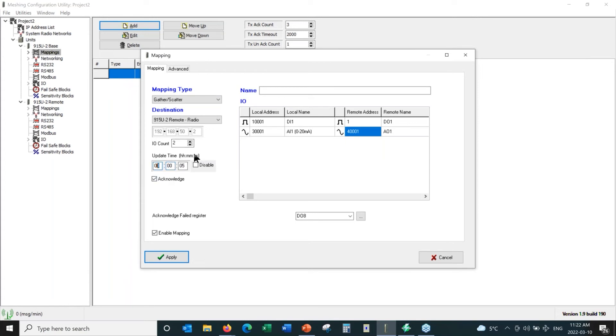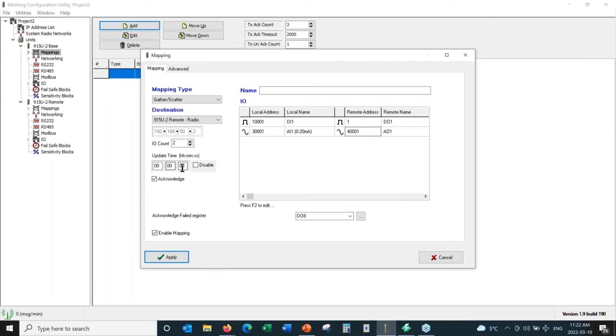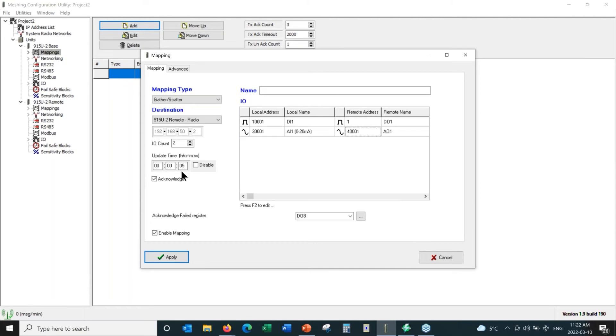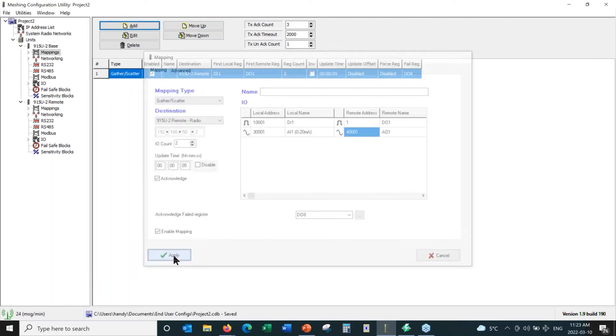With the update time set to five seconds, this radio will transmit every five seconds even if values don't change. For customer installations, we recommend leaving it at 10 minutes, because with hundreds of radios all transmitting every five seconds, you can jam the airwaves with too much bandwidth and some messages may not get through. But for demonstration purposes, I'm setting this to five seconds. Then we hit Apply and we're done.